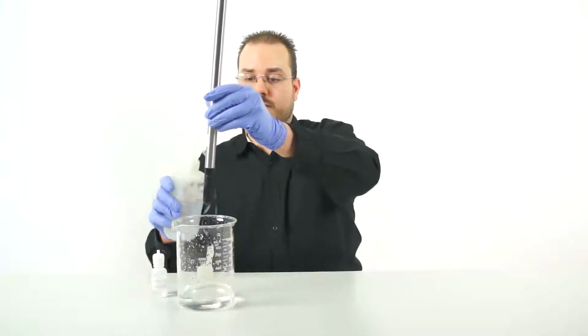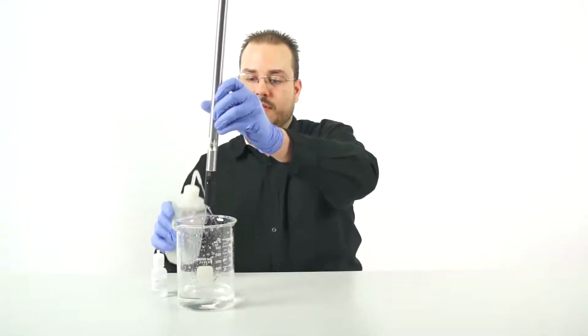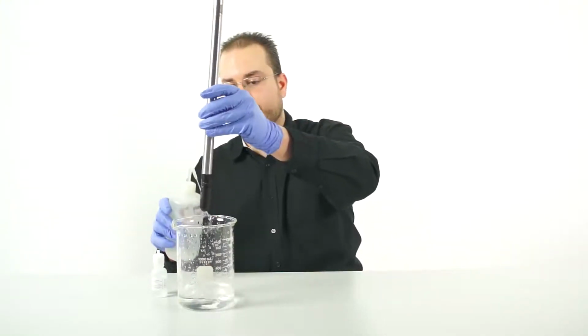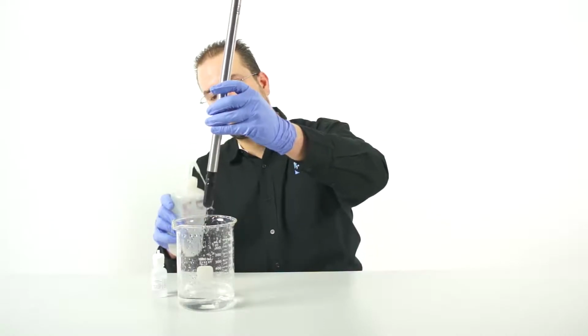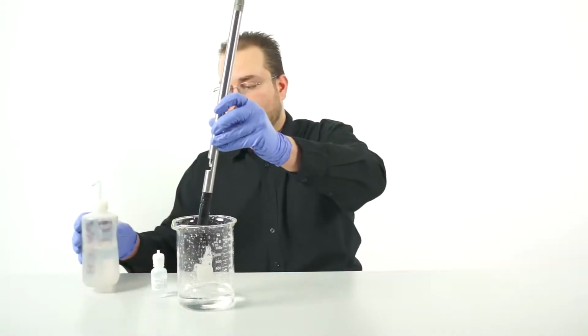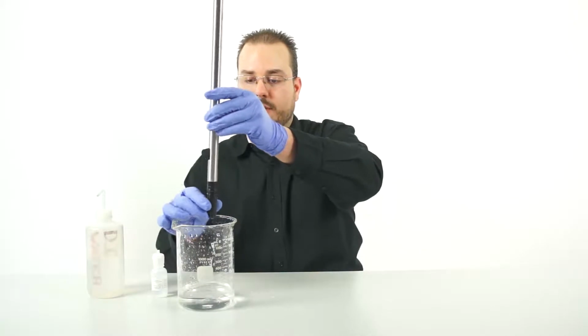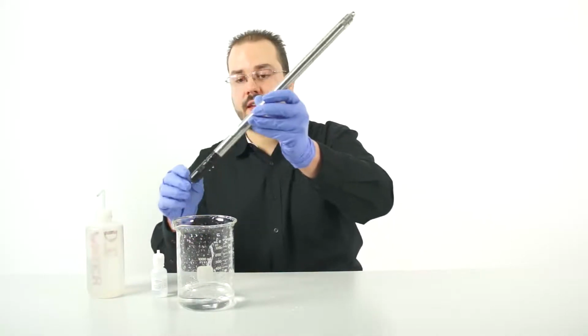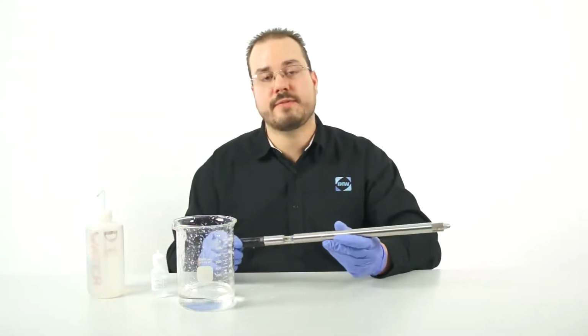After tightening, we'll rinse the entire tip off with DI water to remove any residual reference electrolyte. And the unit is now ready for 2-point calibration. And that is how you change the reference electrolyte in the Temphion smart sensor.